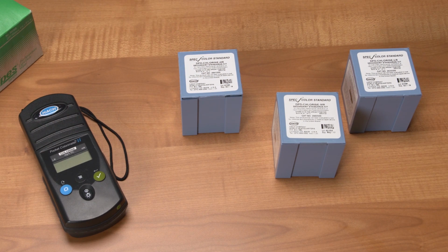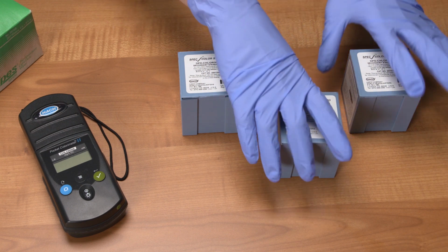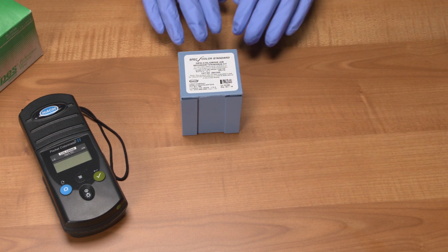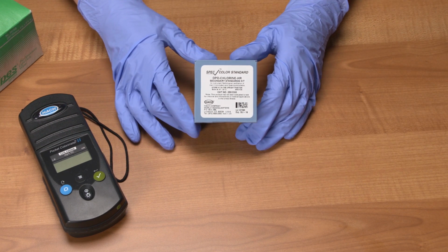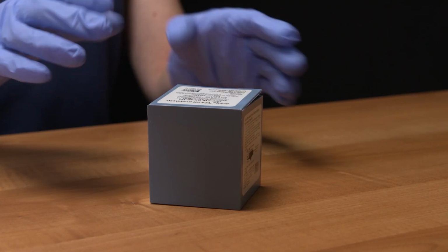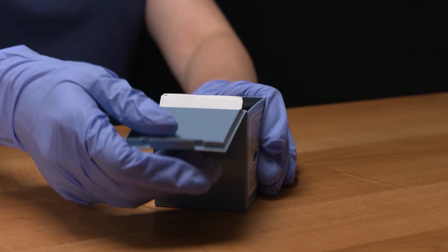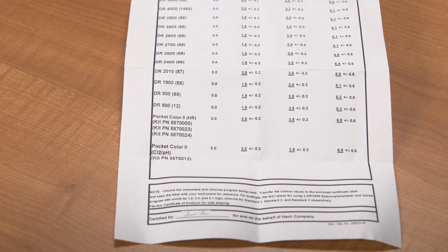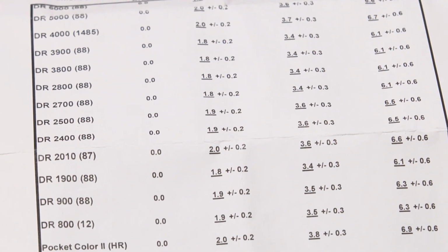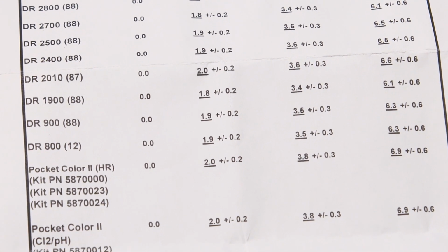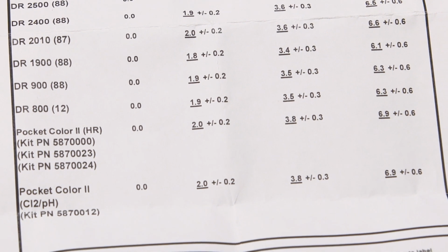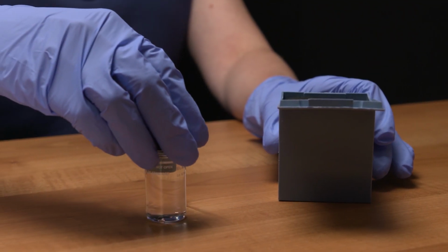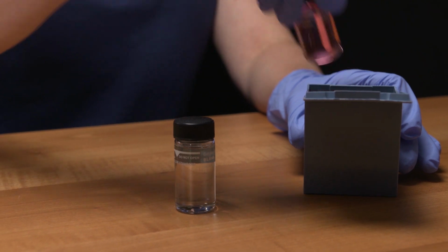Note that some instruments only have low and high range settings and cannot be set to mid-range. The instrument that we are using can only be used with the low or high range standards. We will use high range standards for this example. The secondary standards come as 4 vials with a certificate of analysis. The certificate can be found in the box of standards and lists the allowable measurement ranges for the standards on different instruments. Generally, the secondary standards must be measured to be within 10% of their expected concentrations.